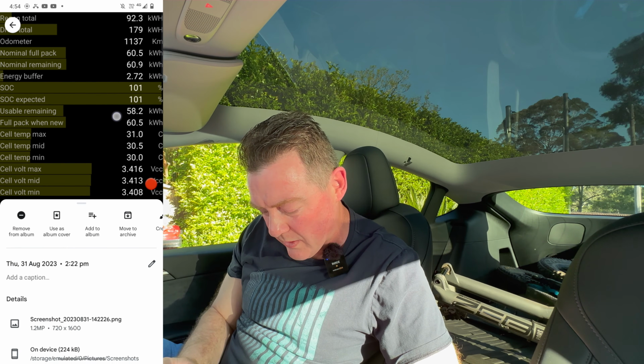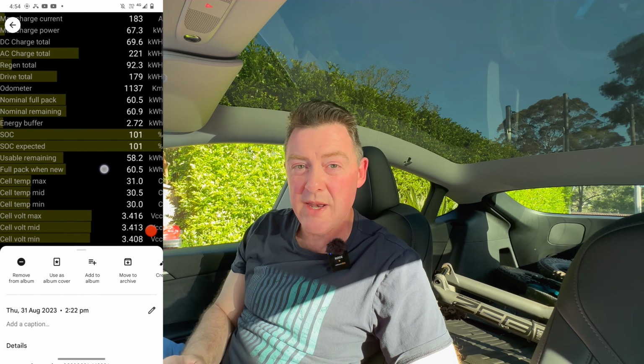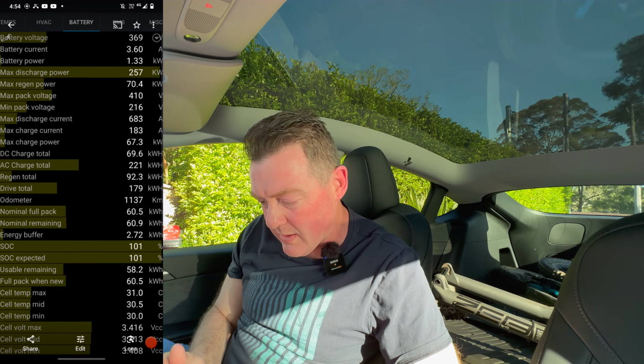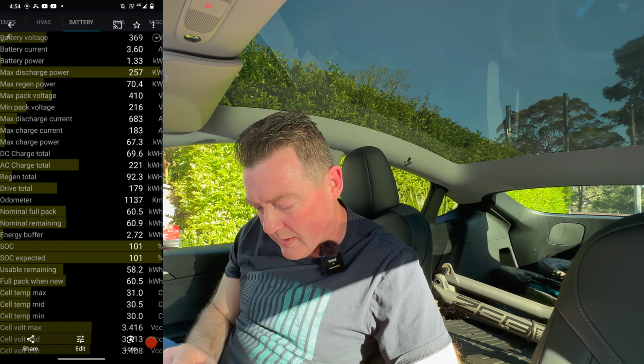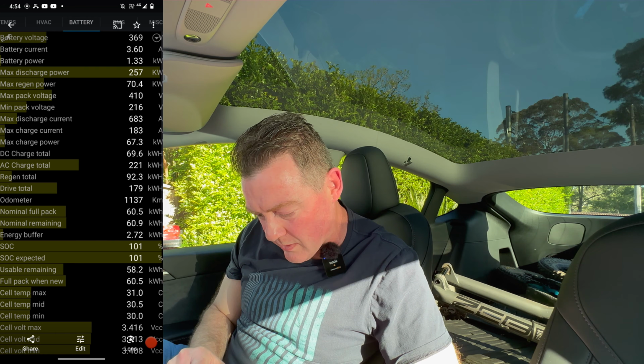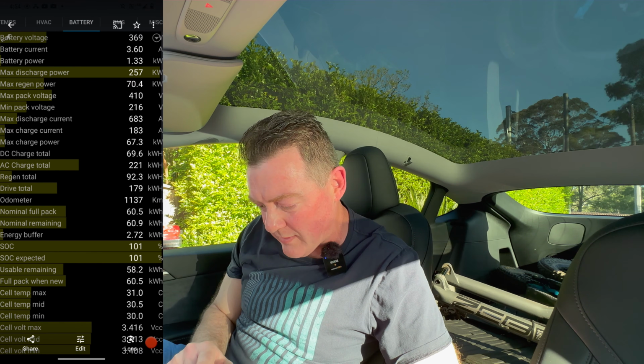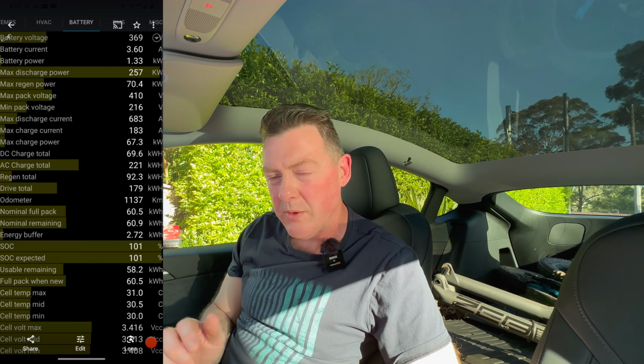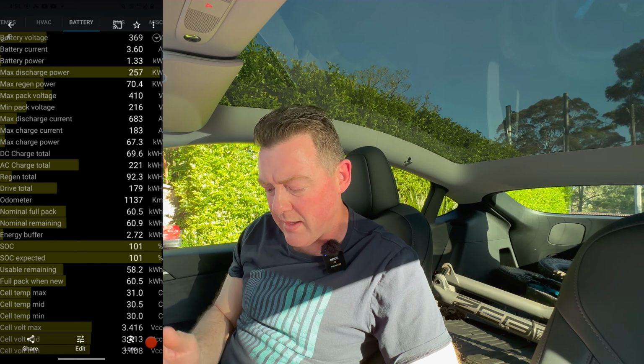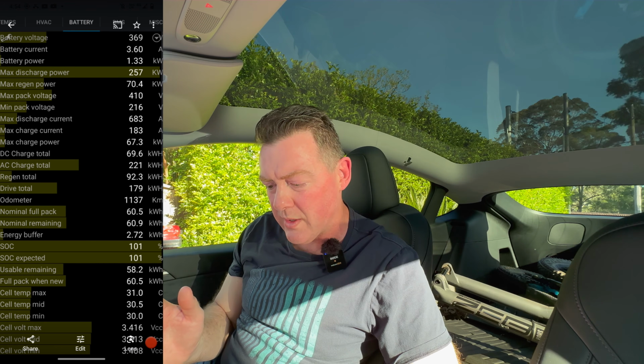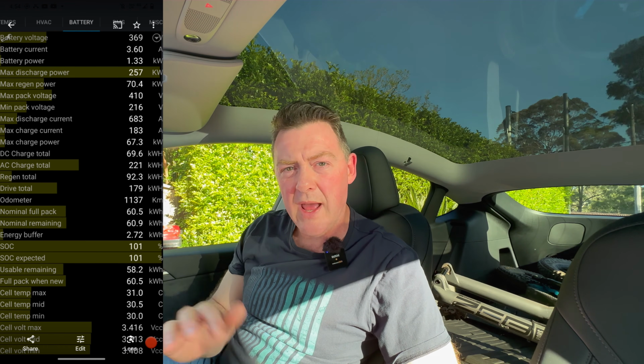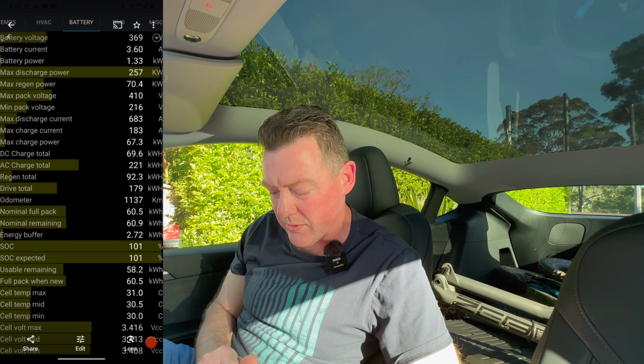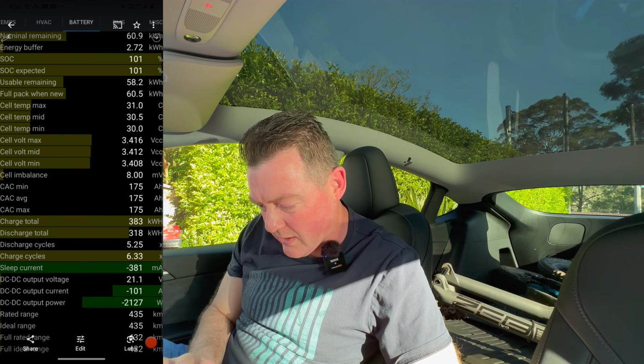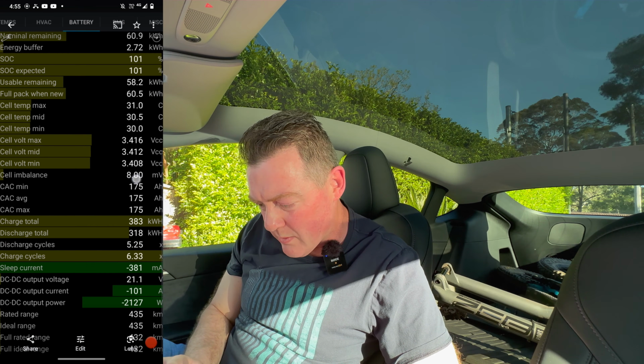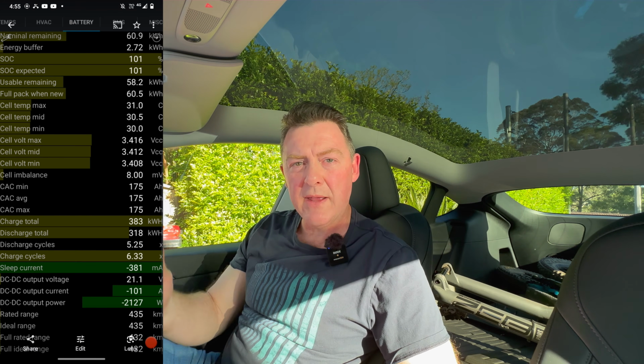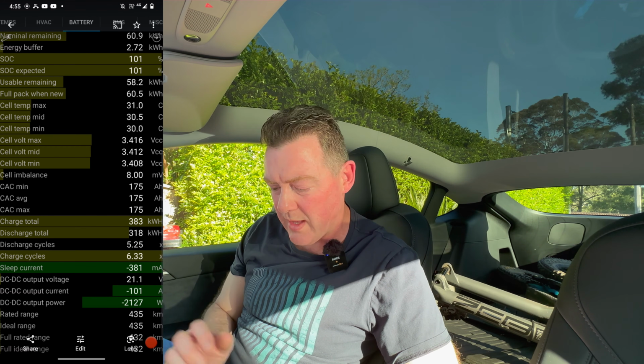And we're starting to see the battery get back to a point. So what's this one here? We've got 31st of August. This was another week, the next Thursday, I took another screen grab. So we can see here, full pack, nominal full pack 60.5, and that's roughly where it sits these days. From 31st of August through, it hasn't really changed much, it really started to settle down. You can see if I go to the next, we've got 8 millivolts there, so the imbalance is getting quite good, and you'll see that improve.